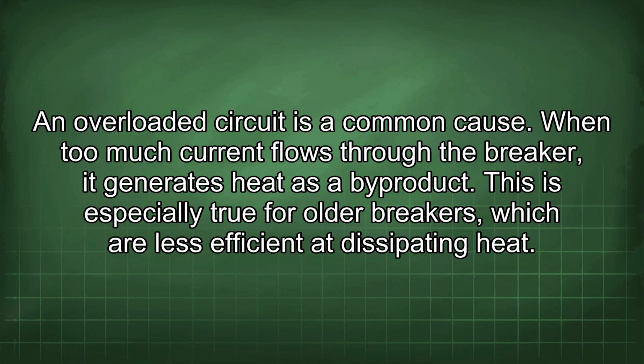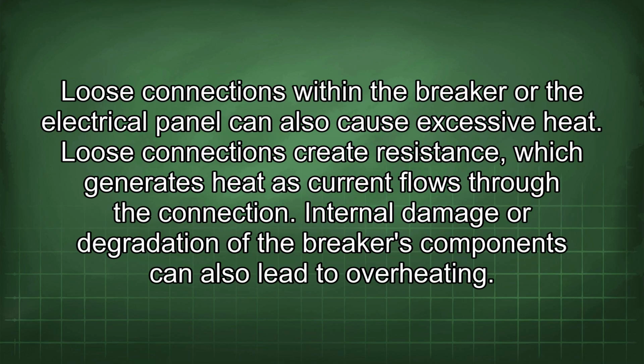When too much current flows through the breaker, it generates heat as a byproduct. This is especially true for older breakers, which are less efficient at dissipating heat. Loose connections within the breaker or the electrical panel can also cause excessive heat. Loose connections create resistance, which generates heat as current flows through the connection.